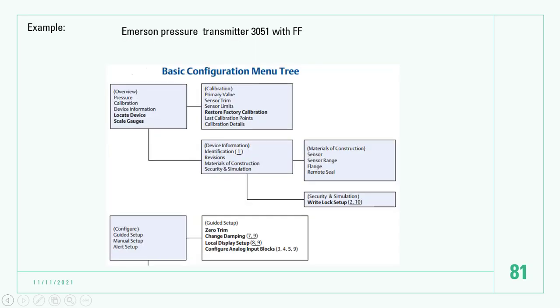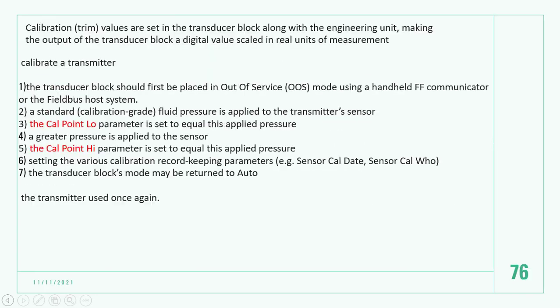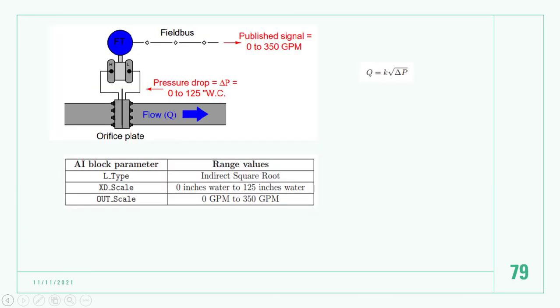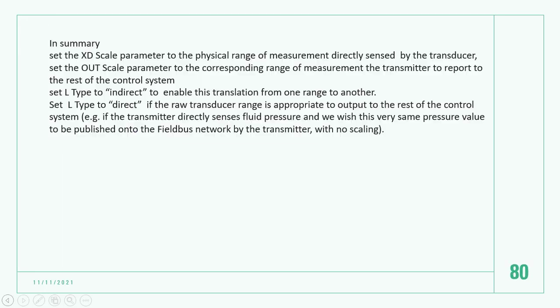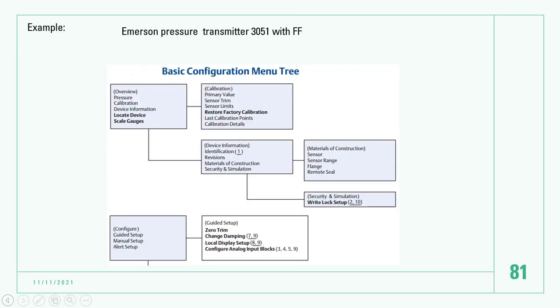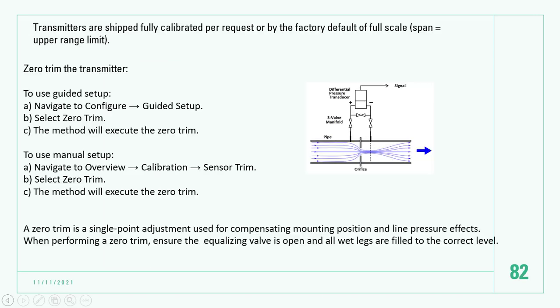Okay. This example, Emerson pressure transmitter 3051 with Foundation Fieldbus. Mark this one. It's important, yeah. It's zero trim. Before, we talked about the flow transmitter or flow calibration and the range. Yeah, this calibration, transmitter range, but we didn't talk about the zero trim. Actually, zero trim is very important. Transmitters are shipped fully calibrated per request or by the factory default of full scale. Okay, zero trim transmitter in the site, you can zero trim.